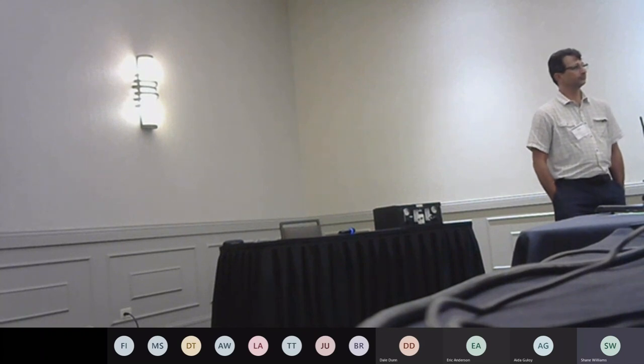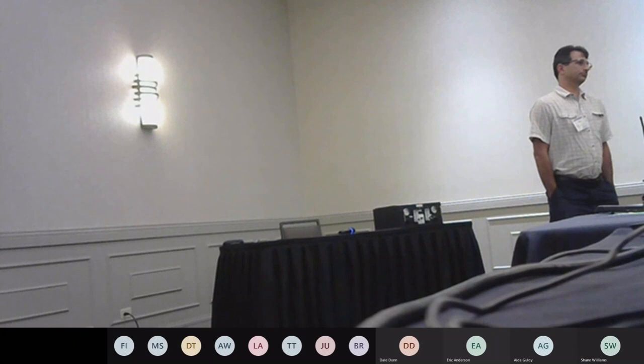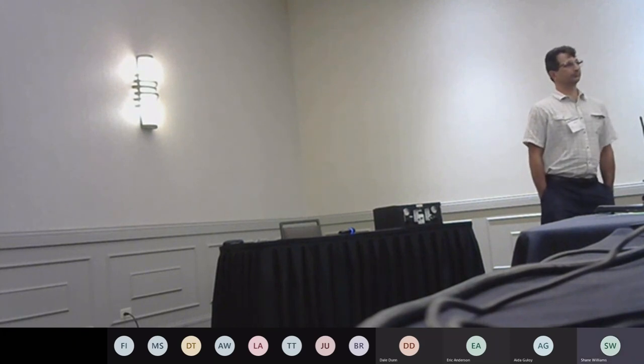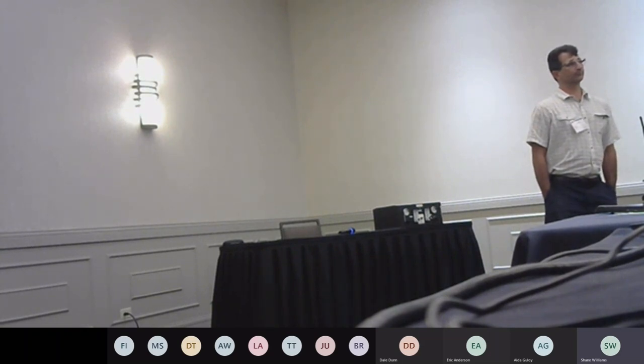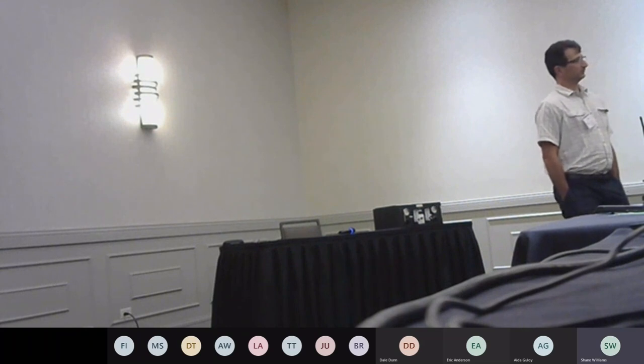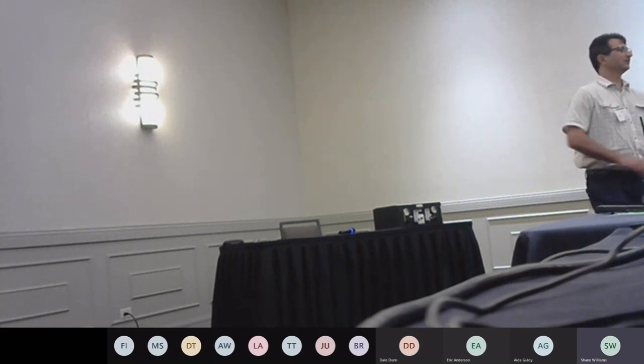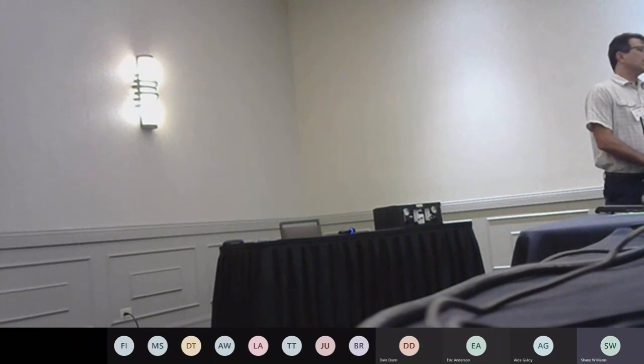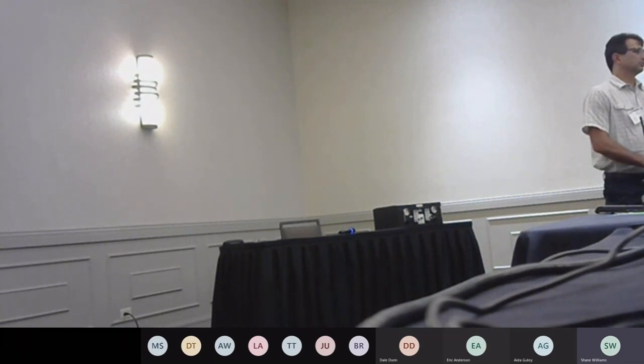One of my agreements with Charlie, we're talking about correcting and correction. Just a reminder, whenever you go through Part 75, make sure when you rerun your test you set the bias back to one. Otherwise, you're just biasing the bias that you keep. That's a good point. The raw data is in the database and you can reread the report. It's not like you have to rerun the test, but you will have to rerun the report. A lot of times, most people who don't catch it have submitted the rebiased bias, but they don't have to rerun the test.